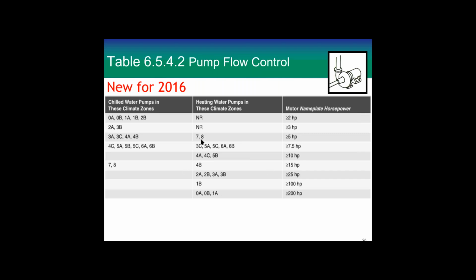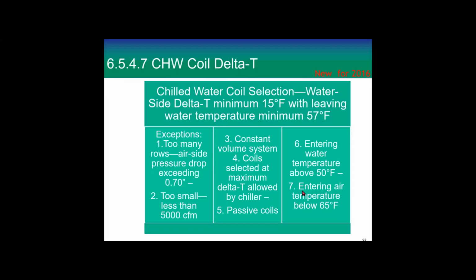Now, the climate zones for heating in 7 and 8, it's 5 horsepower, and then as we go down to the hottest zones, you don't have to put a VFD on the heating side until you're at 200 horsepower, so pretty high.